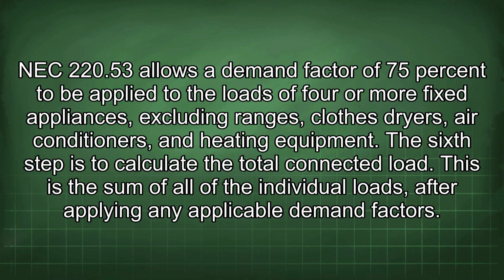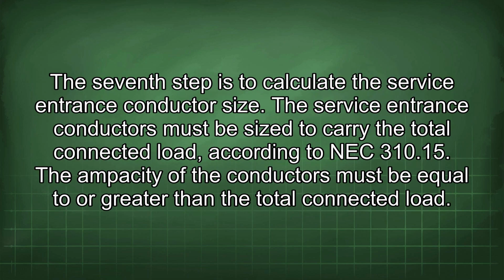The sixth step is to calculate the total connected load. This is the sum of all of the individual loads after applying any applicable demand factors. The seventh step is to calculate the service entrance conductor size. The service entrance conductors must be sized to carry the total connected load, according to NEC 310.15. The ampacity of the conductors must be equal to or greater than the total connected load.